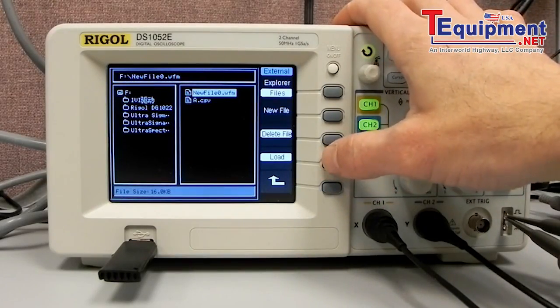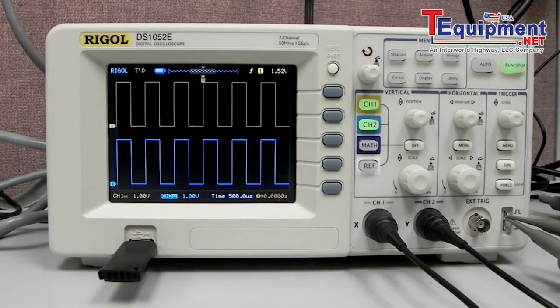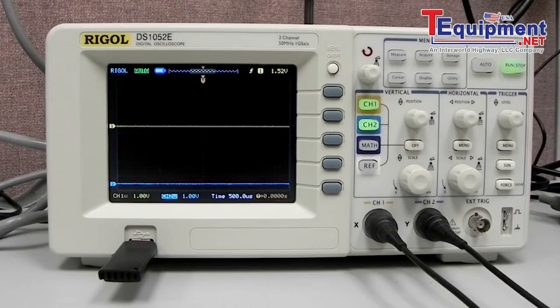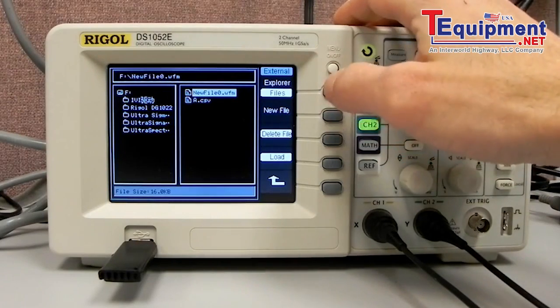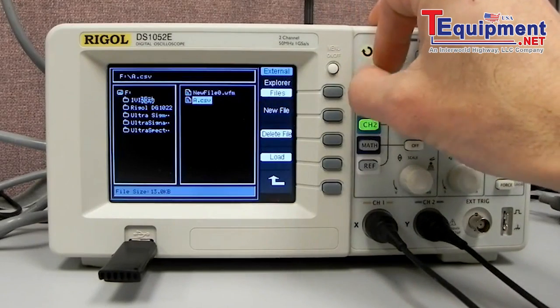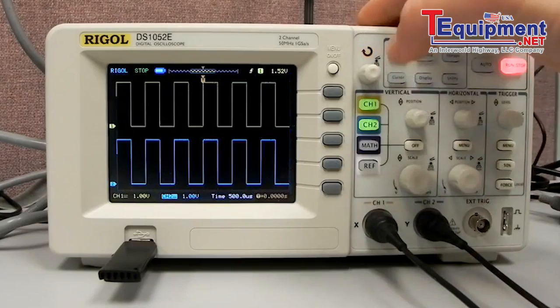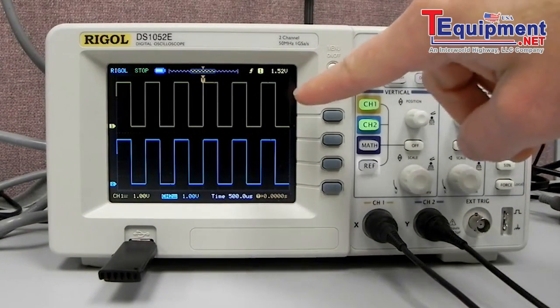We can also load that. I'm going to hit run so we're back to triggering and I'm going to disconnect channel 1 and channel 2. Now let's load that waveform from the external file so I hit storage, external and now I'm going to hit load on the file of interest. I'll select that new file waveform that we just collected and hit load.